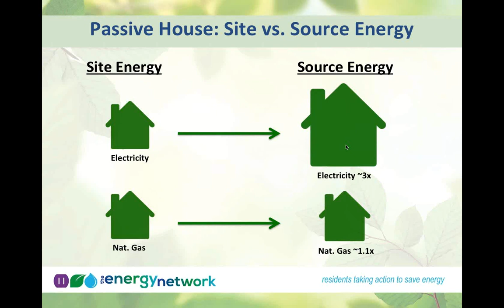To sum that up: if we were just looking at site energy for two hypothetical buildings, one powered by all electricity, the other by natural gas, and they use the same amount of site energy, meaning the meters read the same, when you convert to source energy, the all-electric house is using about 3 times that much energy, and the natural gas house about 1.1 times the energy. It's not to say electricity is a poor choice, just that you need to factor source energy into your calculations. Don't just think about what's read at the meter.